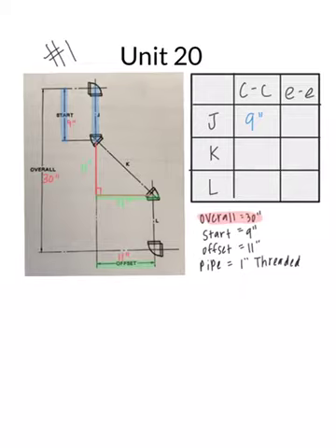I'm going to write this down at the bottom just so I have some work. To find K, we did 11 inches, multiplying by 1.414, which is the constant for a 45. I'm typing that in my calculator right now. 11 multiplied by 1.414 equals 15.554 inches.